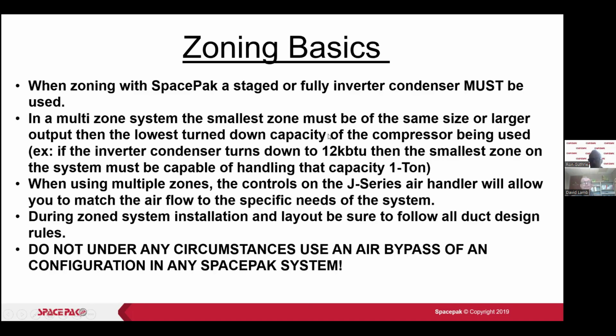The smallest zone must be the same size or larger output than the lowest turn down capacity of the compressor being used. Okay, so if we have a 2-ton and the first zone is half of that 2-ton, then we want to make sure we have turned down to at least 50%. Okay, so that's really what we're looking at there.